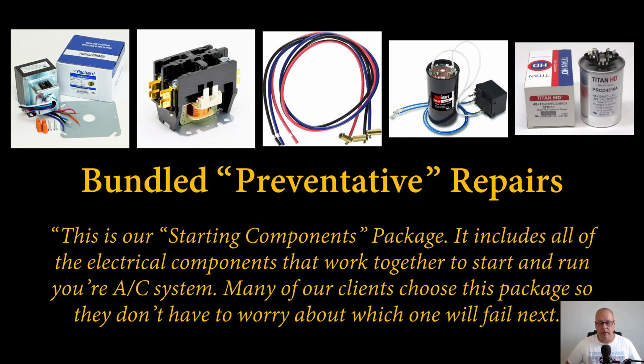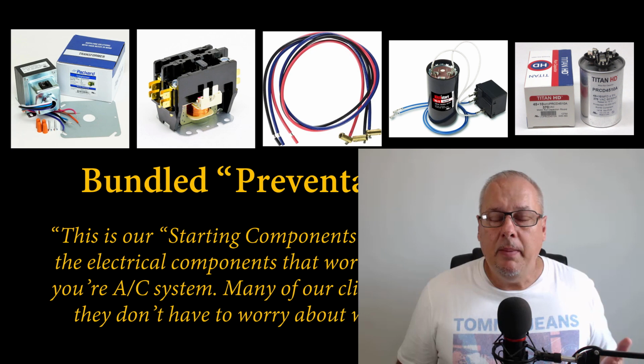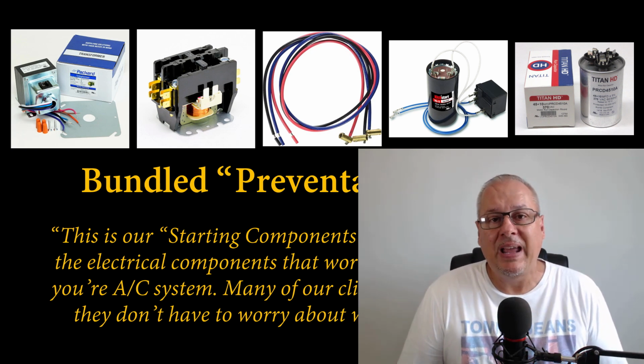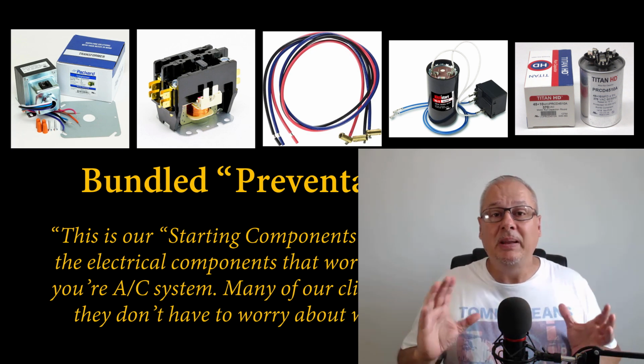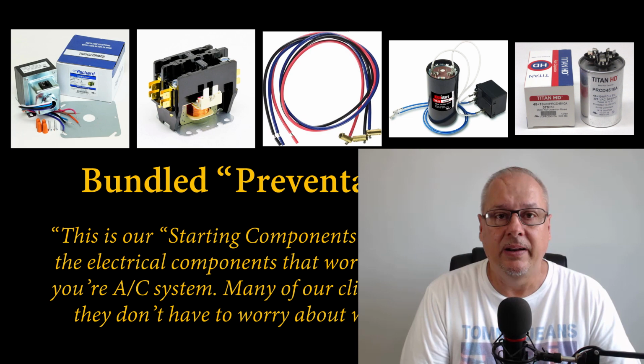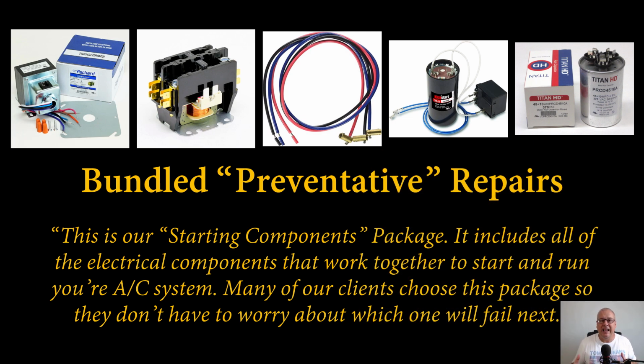For example, bundled repair services — think about it. When the run capacitor goes on the condensing unit, isn't it around the same time the contactor starts to go? Those parts tend to fail around the same point in their lifespan. What could we pre-package and offer customers so they don't need you back for unnecessary repairs later? So here we've got a contactor — we could go with a more robust one. We've got compressor leads — if they're starting to turn green, why not take care of that now, rather than wait until it burns up and ruins the compressor? What about a hard start kit — has the equipment reached the point where this could help the compressor cycle more efficiently?